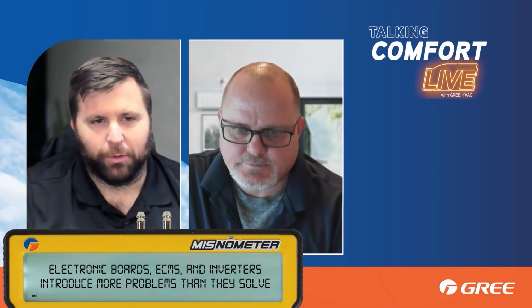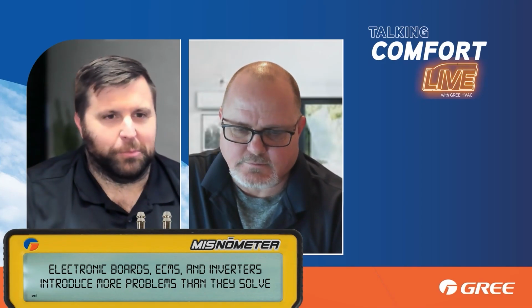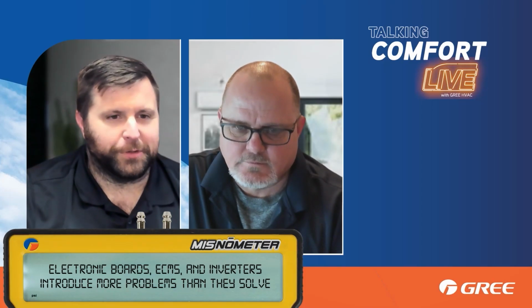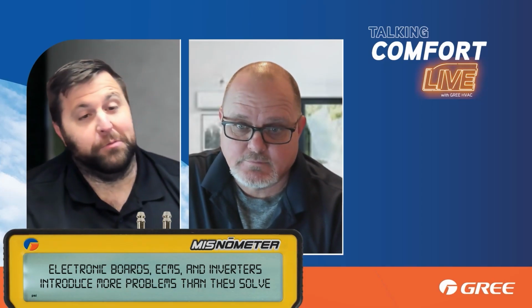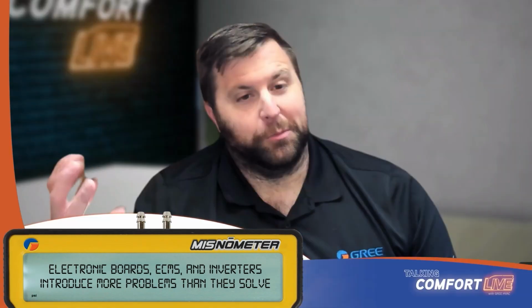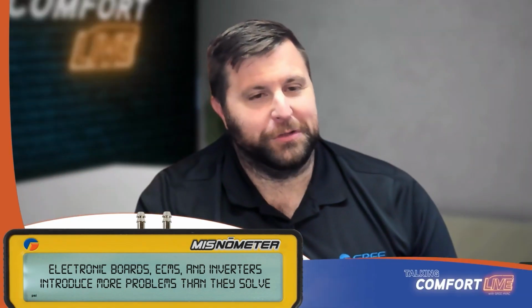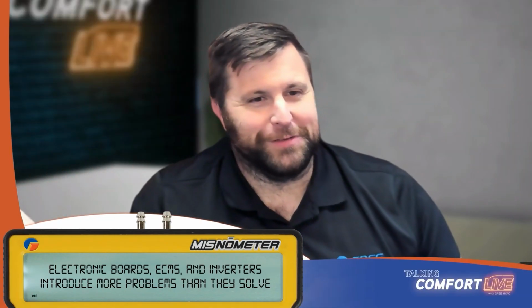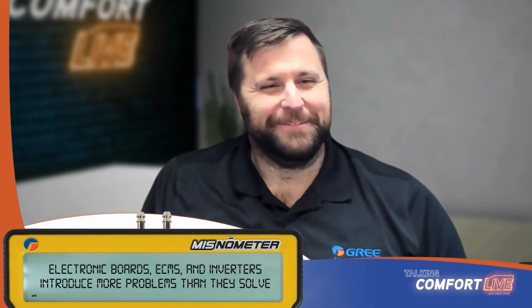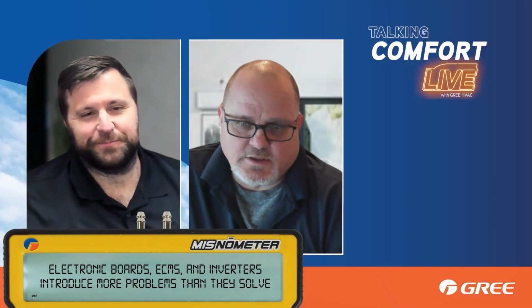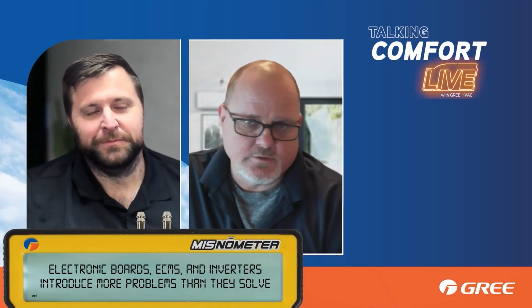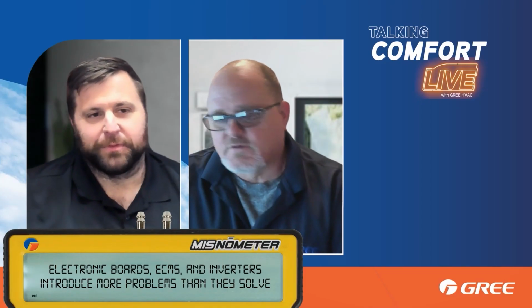So I've got a bad blower motor. Not really. The motor itself is probably all right. Now, can you get an ECM module separately, pre-programmed and all the rest of that, and put it in yourself? I don't know. Maybe it depends on the manufacturer. It does depend on the manufacturer. Some only sell the whole kit and caboodle, and some sell you just the module. It just depends on how it comes.